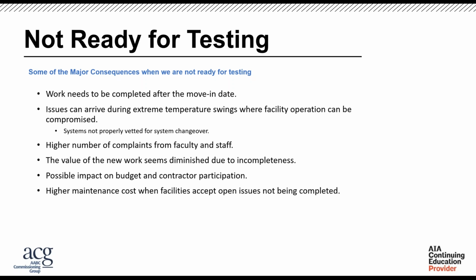and when we found these issues, we weren't able to resolve them in time. One of the big things is our graphical interfaces aren't complete at the time of testing. They'll get completed, but if you have troubles, it's hard to really identify and close out some of the trouble. And a big thing is non-communication. A lot of times when you're not ready for testing, that communication is never given back. So you'll have a commissioning provider make that trip only to find out, hey, we weren't ready, no one communicated back. So that's an additional expense.